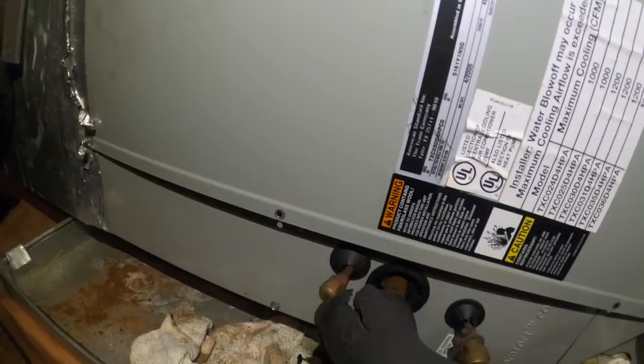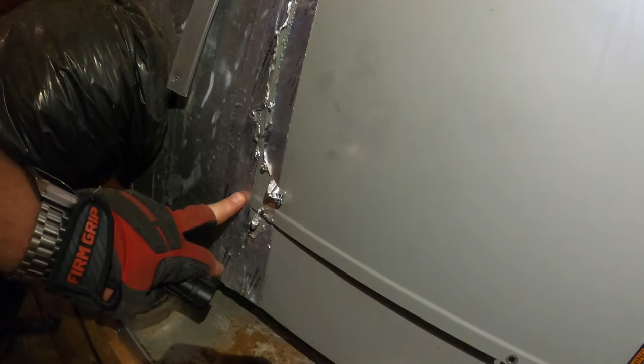As you guys can see, I've gotten a few of the screws out, but the first indicator that whoever this other company was didn't pull this to try to inspect the heat exchanger is the fact that there's one screw still back here behind a piece of this plenum that overlaps the end of this coil, which that's not the way you're supposed to mount one of these. You're supposed to flange it and then mount it back here on your lips off the back of the coil.